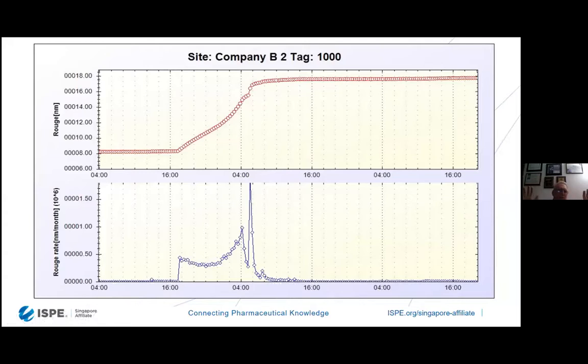We're going to add the sodium hydroxide. We'll have no problem. We're going to rinse out our system and everything is going to be fine. Well, that's not what the Rouge monitor sees. The Rouge monitor actually shows that, even though they added the sodium hydroxide here, it took almost 24 hours for the system to get back to its pre-level before it administered the chemicals.